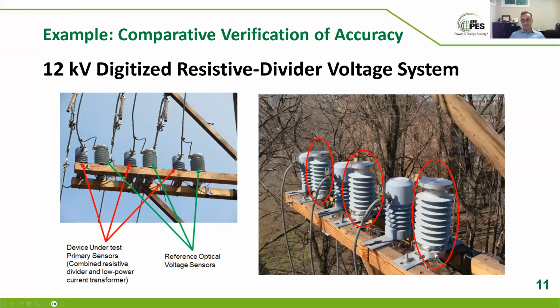Resistive dividers, especially depending on their secondary cabling and their ratio, often enough don't have a very wide bandwidth, maybe a few hundred hertz. They're good for power frequency often, and if you're careful, the phase could be okay too. And here the idea was the utility wanted, this is close to a capacitor switching place, so they were interested in a bit wider performance, seeing switching transients reliably. Basically the idea there was combining a resistive divider, which is usually less expensive, with some electronics and advanced signal processing and error compensation, and producing IEC 61850 sampled values at 4.8 kilohertz with decent bandwidth, but decent in this case means maybe up to 2 kilohertz.